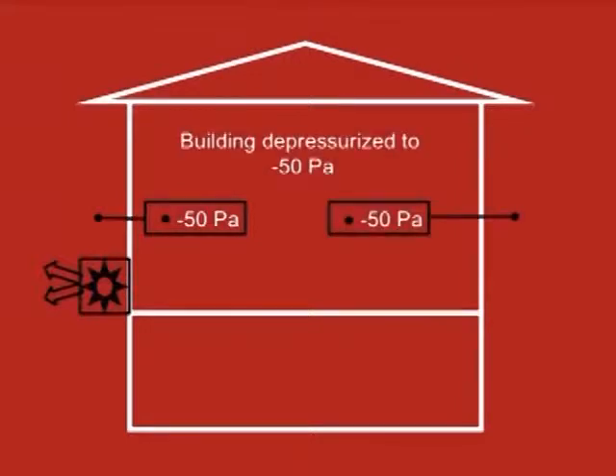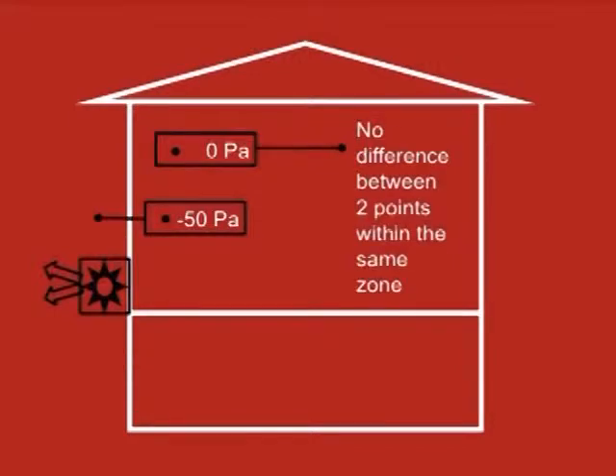Let's look at a very simple building. It is a single room, single story home with a crawl space and a cold attic. Depressurizing the building to minus 50 pascals results in a 50 pascal pressure difference across the building's exterior walls. If we measure the pressure difference between two places within the single room, the pressure difference should be zero.